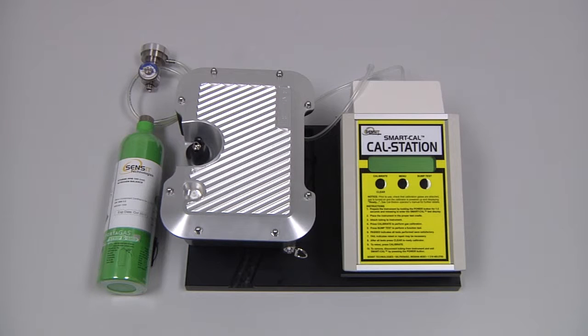To perform an automatic calibration of the IRED, we will need the IRED itself, along with the cal station with an instrument hose, and a regulator with the cal adapter and the calibration gas, which is 100 parts per million methane nitrogen balance.